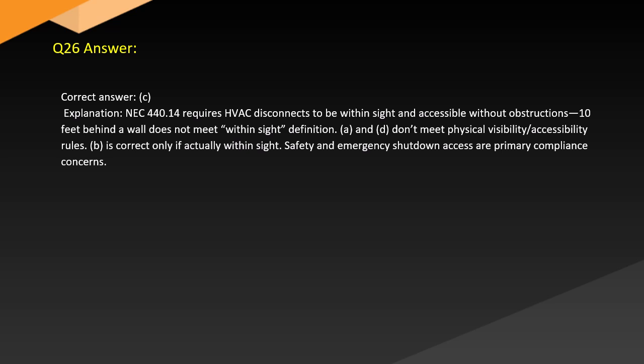Answer. Correct answer: C. Explanation. NEC 440.14 requires HVAC disconnects to be within sight and accessible without obstructions. 10 feet behind a wall does not meet the within sight definition. A and D don't meet physical visibility and accessibility rules. B is correct only if actually within sight. Safety and emergency shutdown access are primary compliance concerns.